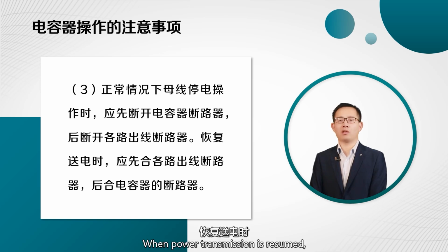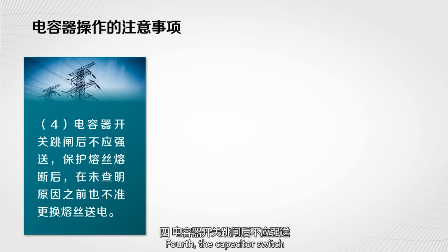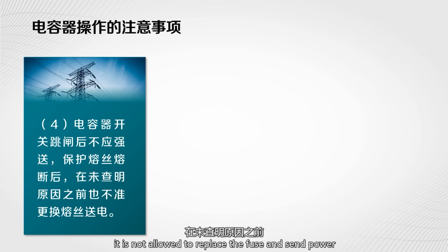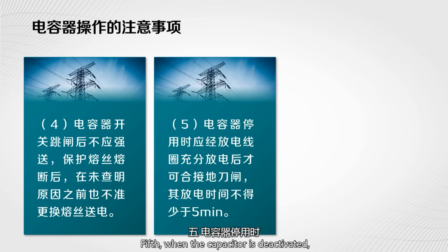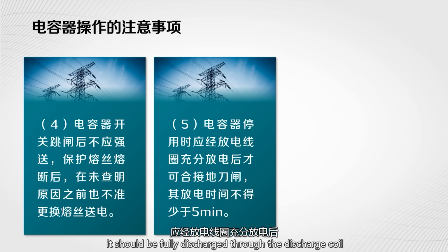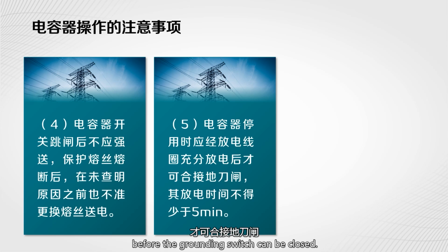When power transmission is resumed, the outgoing circuit breakers of each route should be closed first, followed by the circuit breaker of the capacitor. Fourth, the capacitor switch should not be forced to send after tripping. After the protective fuse is blown, it is not allowed to replace the fuse and send power until the cause is identified. Fifth, when the capacitor is deactivated, it should be fully discharged through the discharge coil before the grounding switch can be closed. The discharge time should not be less than 5 minutes.